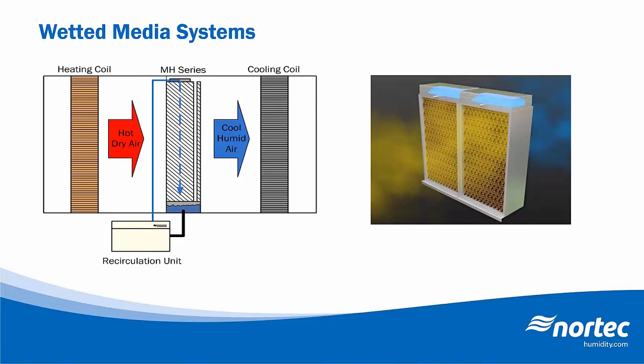Now, a consideration that you should keep in mind when using an evaporative media system is the controllability. So the media itself will require a time to fully wet and fully dry. So the system will be a little bit slower to respond to changes in demand. So depending on your requirements, you may also need to implement a different control strategy, something like face and bypass damper, if you do need tighter control of the leaving air conditions.